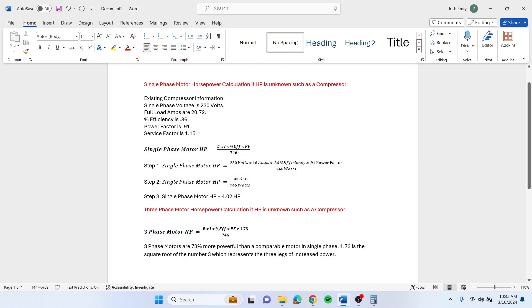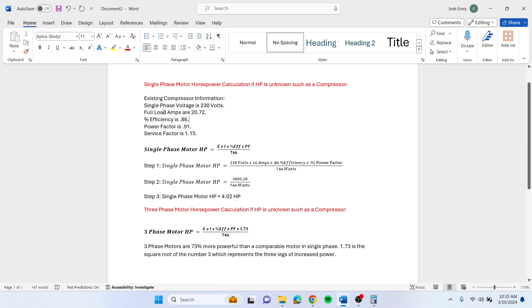Let's say this is the information we have from the compressor. The full load amps are 20.72, that's what we're reading right now with our amp meter. Our efficiency is 0.86, our power factor is 0.91, and it's 230 volt single phase.